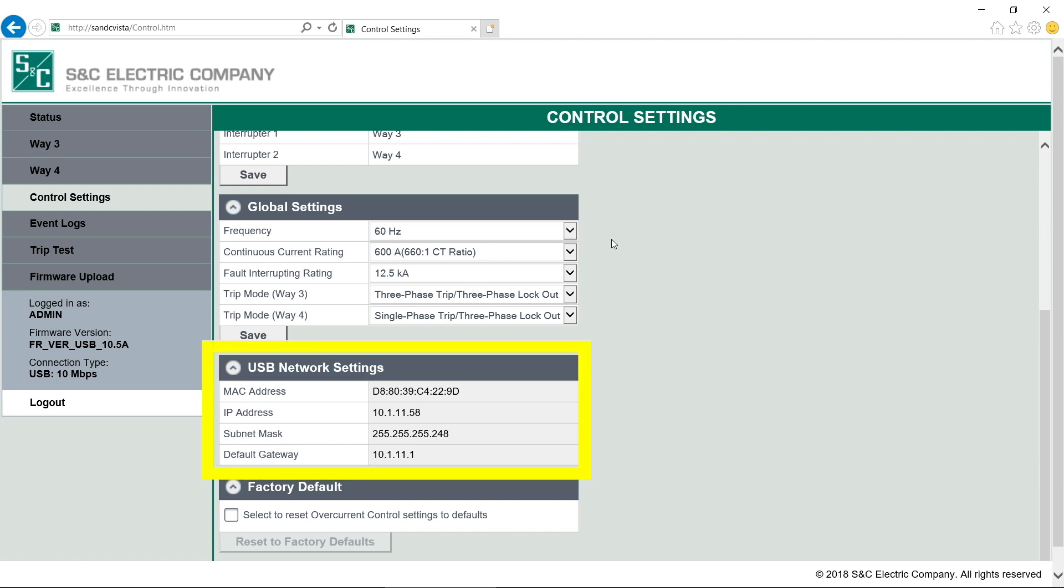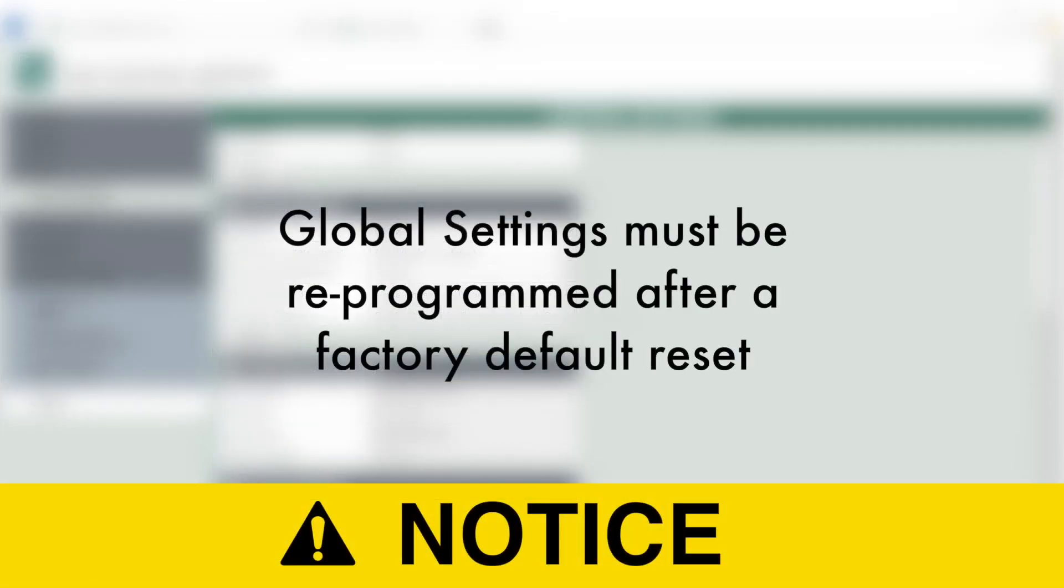The USB network settings is where we can find the MAC address, IP address, subnet mask, and default gateway information. And finally, here is where we can reset the control settings to their factory defaults. Simply click the checkbox and then click the Reset to Factory Defaults button. Notice, S&C programs the global settings at the factory. The factory default reset setting will restore the settings back to the overcurrent control's pre-programmed state. You must reprogram the global settings for the overcurrent control after performing a factory reset to match the configuration of the Vista switchgear that the control is monitoring and controlling. Passwords are also reset after factory default settings are restored.